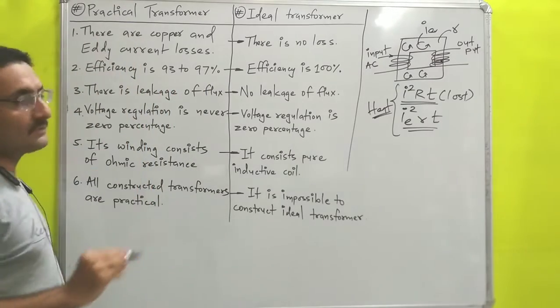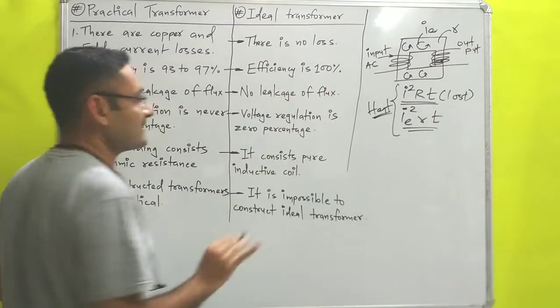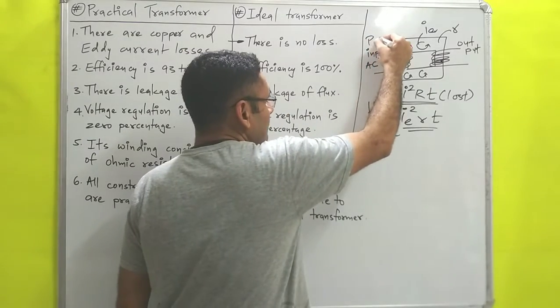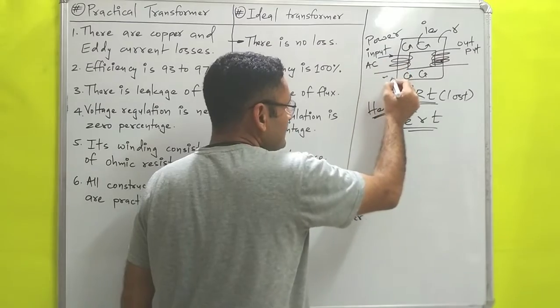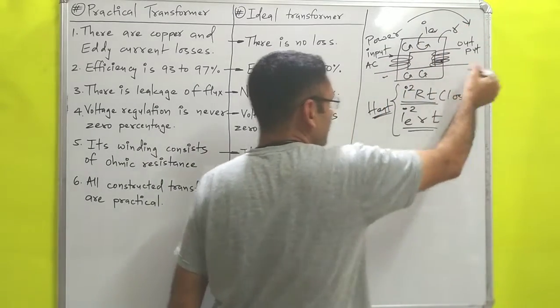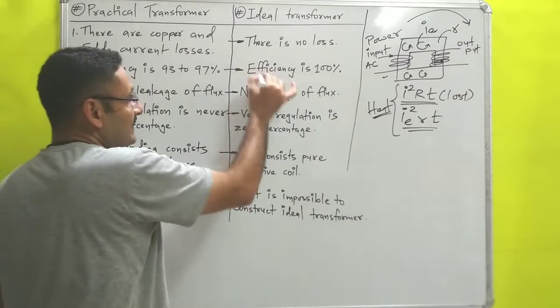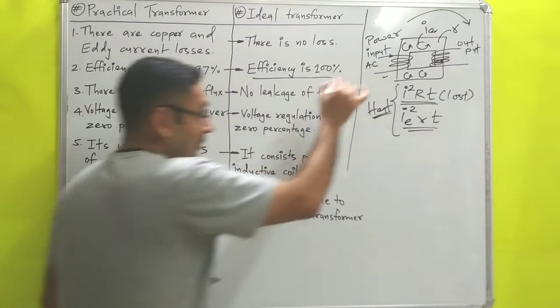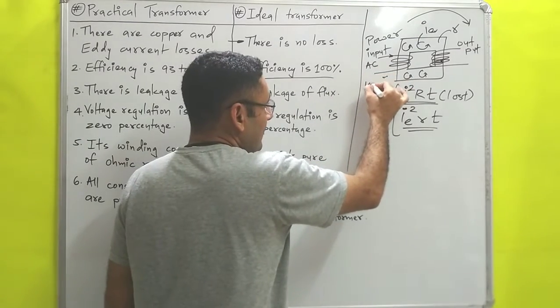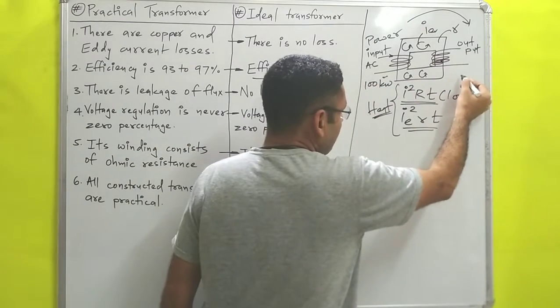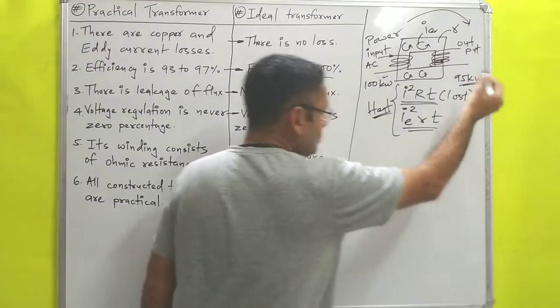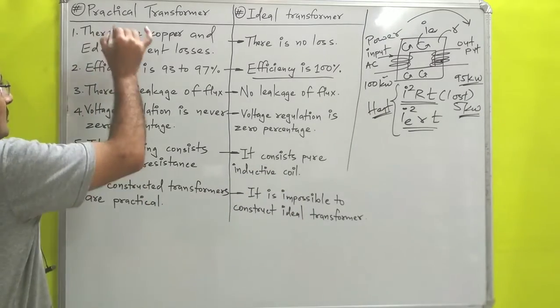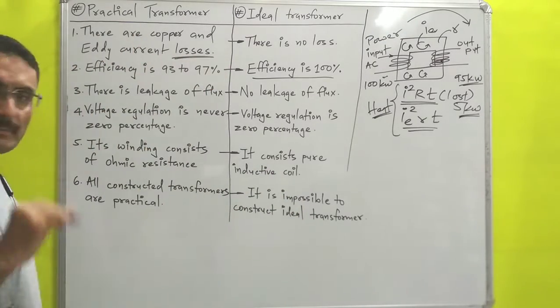Next, efficiency is 93% to 97% for a practical transformer, whereas efficiency is 100% for an ideal transformer. In the case of an ideal transformer, whatever power you supply to the primary side, the same power you get on the secondary side. In a practical transformer, if you supply 100 kilowatts, only about 95 kilowatts are transmitted because 5 kilowatts are wasted as losses.